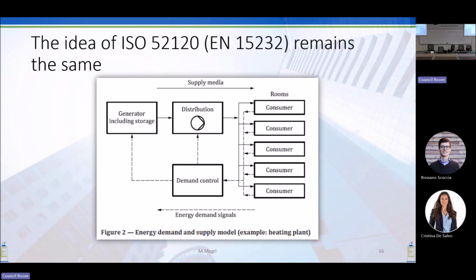This is not so true, because sensors can also be read only in theory, but in practice I can show you the BMS - if I have troubles and a sensor is not functioning, I can force a temperature on a single sensor. It can be a temperature, pressure, differential pressure, or relative humidity sensor, anyway. I can force them. I can force not only the output of a controller but also the input.